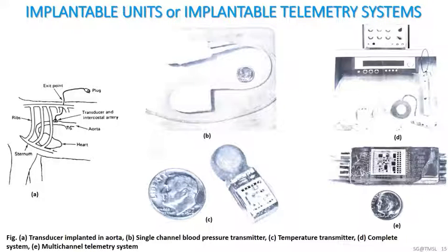And this is the cutaway view of a single channel temperature transmitter, and a 1.35 volt battery is contained inside the antenna loop at the top. Inside one of the three hybrid packages is shown here, that is open here.